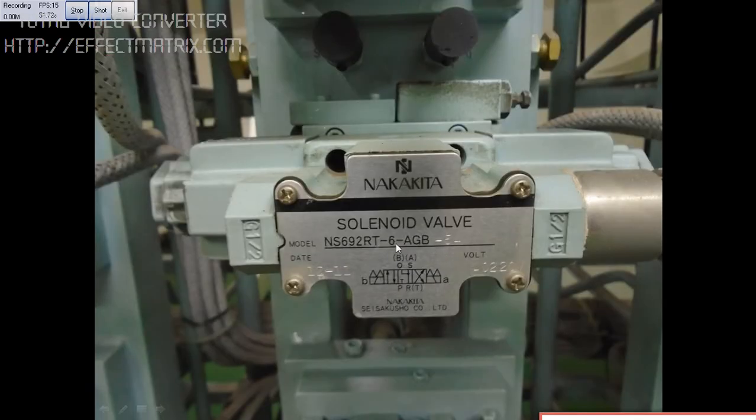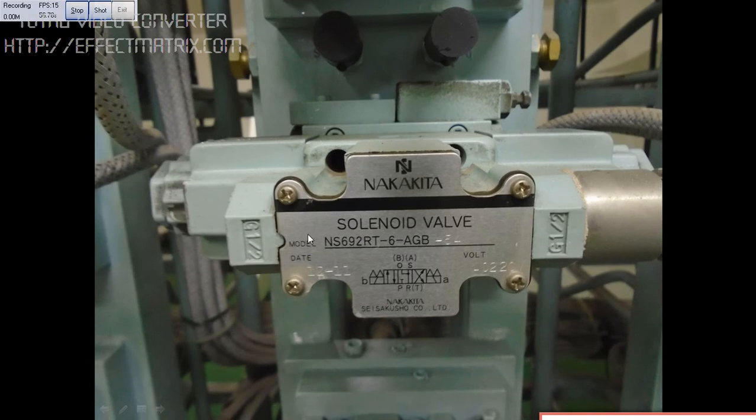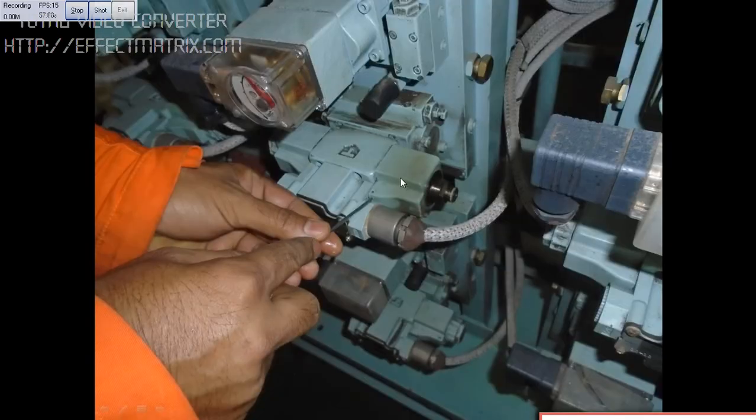This is the solenoid valve. We have got two coils on both sides which is used for opening and closing. You can see the coil has got heated up, now it is not working.